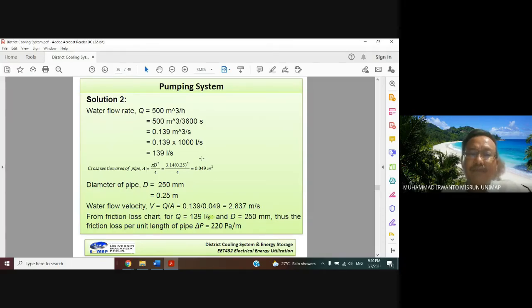So water velocity can be obtained from this formula: Q over A, flow rate over cross section area of the pipe. Please take the unit of Q here in cubic meters per second: 0.139 over cross section area 0.049. So the water velocity is 2.837 meters per second.